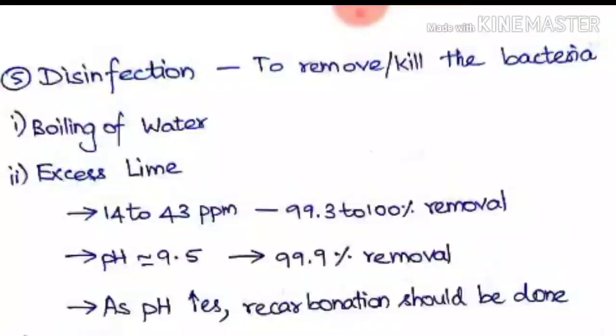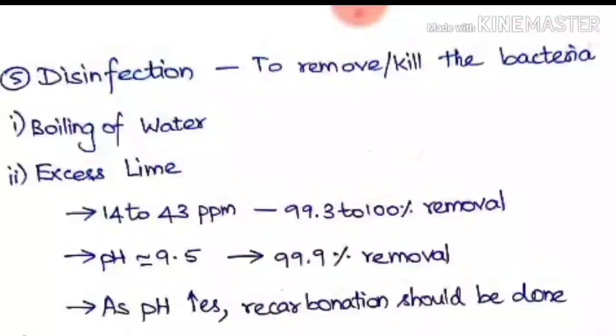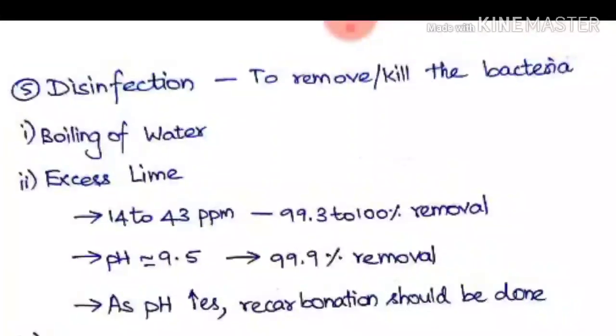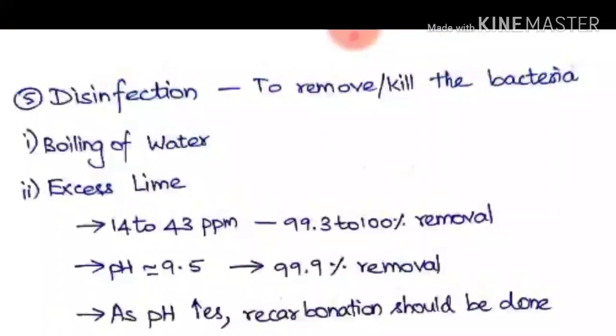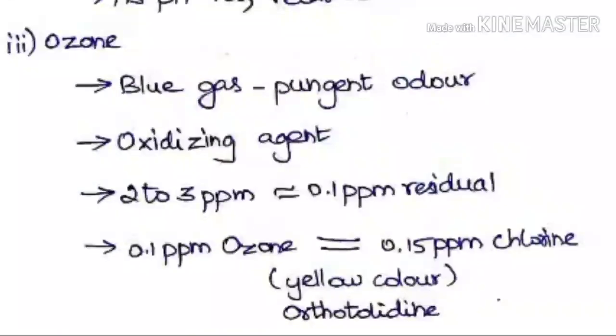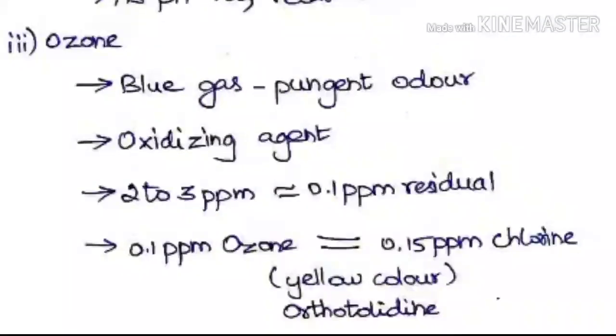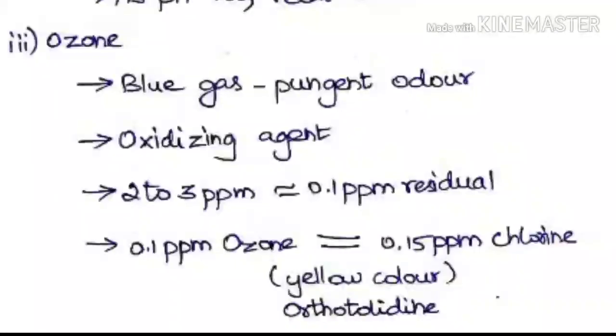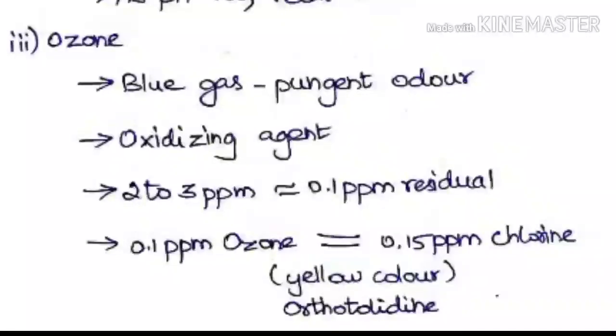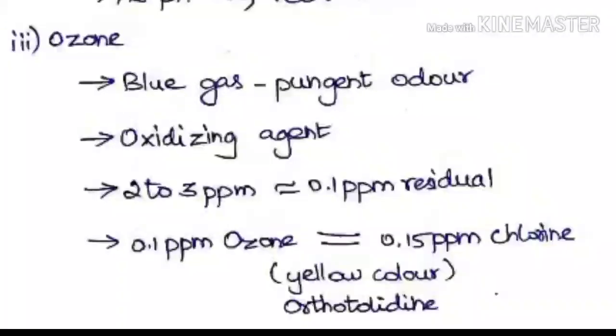Even at pH 9.5 the removal will be 99.9%. Therefore, if we are using excess lime, recarbonation should be done to reduce the pH and bring it to nearly 7 before providing to the distribution system. The third method is ozone. When ozone gas is introduced into the water it also acts as a disinfectant. It is slightly blue in color and is a pungent-smelling gas.